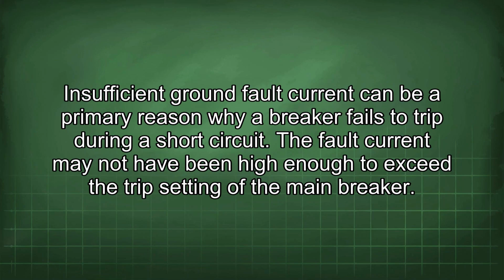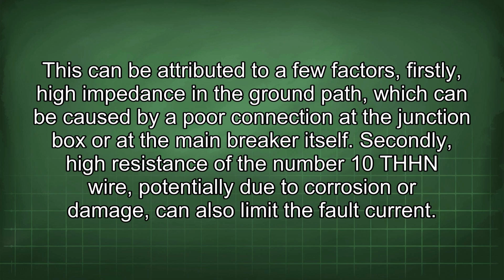Insufficient ground fault current can be a primary reason why a breaker fails to trip during a short circuit. The fault current may not have been high enough to exceed the trip setting of the main breaker. This can be attributed to a few factors. Firstly, high impedance in the ground path, which can be caused by a poor connection at the junction box or at the main breaker itself. Secondly, high resistance of the number 10 THHN wire, potentially due to corrosion or damage, can also limit the fault current.